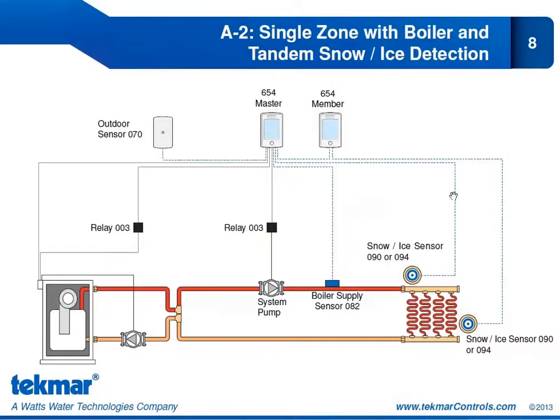Because we have 2 snow ice sensors, we of course need 2 654s. And you'll notice we have labeled one of them as the master and one of them as the member. So the master 654 is the control that is operating the boiler, it's operating the system pump, it's getting the boiler supply data. And the member 654 is only connected to that secondary snow ice sensor, and it's communicating that information to the master control. So as I said, we will discuss this at length later in the presentation. This is just a quick preview of it as it pertains to application 2. So application 2, we are operating this modulating boiler. This modulating boiler requires an enable signal. And remember, when we have that enable signal, we require an isolation relay. Another isolation relay is required to operate our system pump.